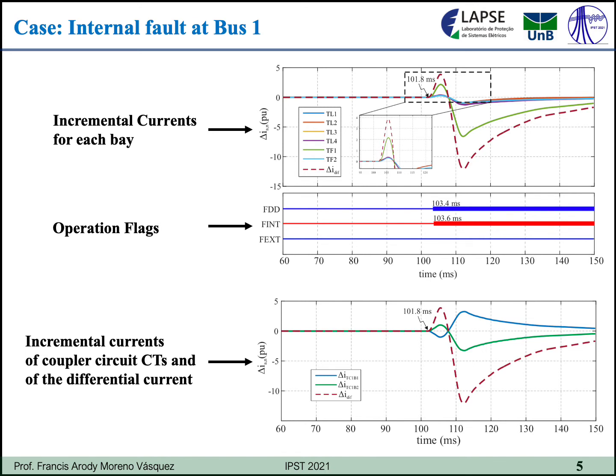Thus, it is confirmed that the fault occurred at bus 1, and all the feeders connected to this bus must be disconnected. By the way, this is the last step. We must identify the feeders to be disconnected, and for that, the status of the circuit breakers and disconnect switches must be known in order to disconnect all feeders connected to the faulted bus.